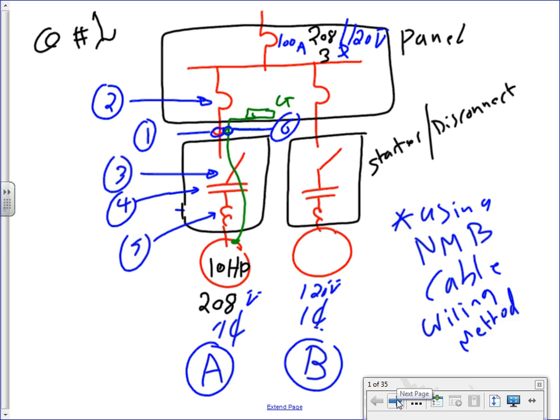The example we're using has a 10 horsepower motor and a 5 horsepower motor. One is connected at 120 and the other at 208. Both of them are single phase. How do you get single phase 208? Anybody? You get two hots from a three-phase system. That's single phase. The power system is 208/120 three-phase, and the wiring method is NM-B. Find the following. That's what you're going to see on the test. Question number one. Any comments before we start?